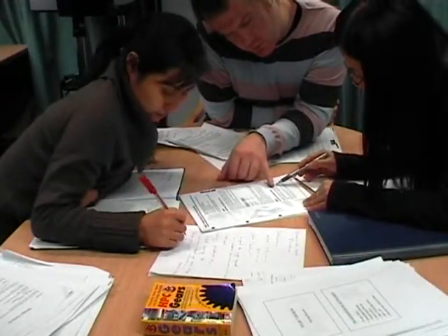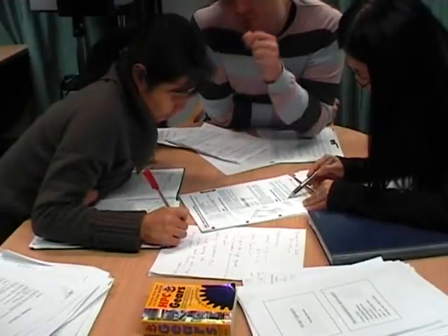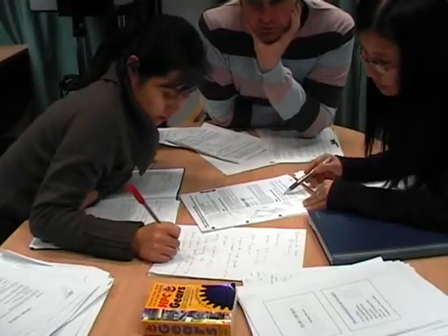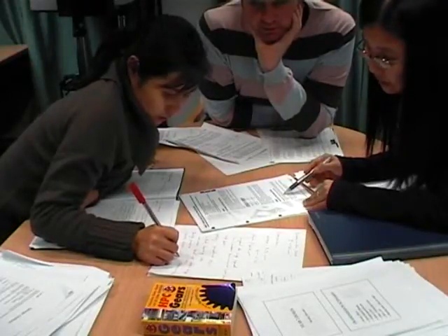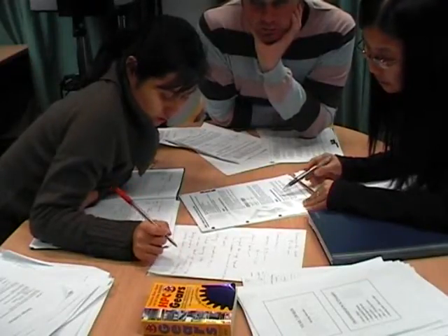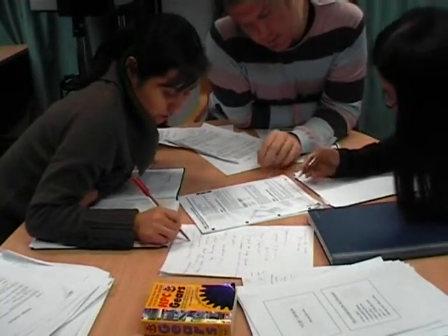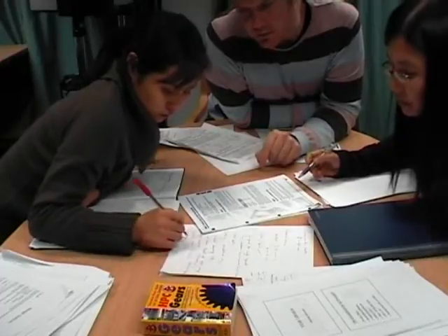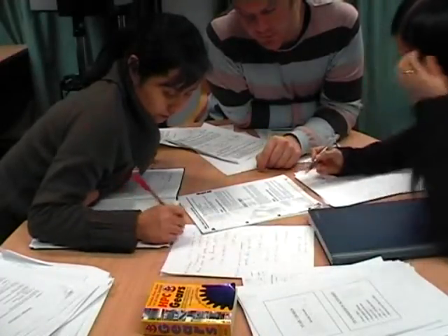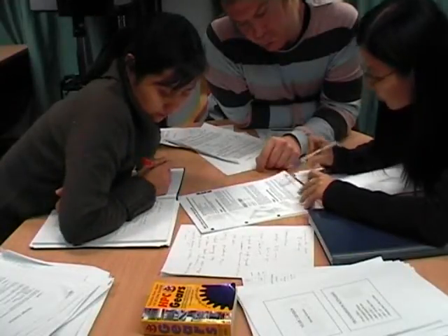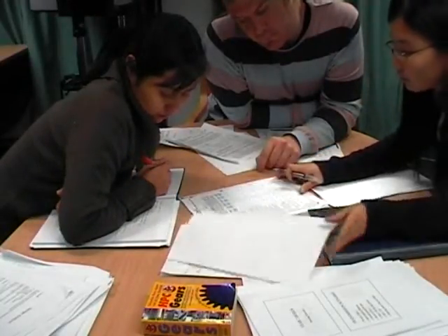Okay, so the service factor is a factor multiplied by the power requirement. We have a total design power of 15 kilowatts multiplied by 1.5, which is 22.5 kilowatts, our design power. If I understand that correctly, that's what we have to select our drive for. Okay, we've done step 2.